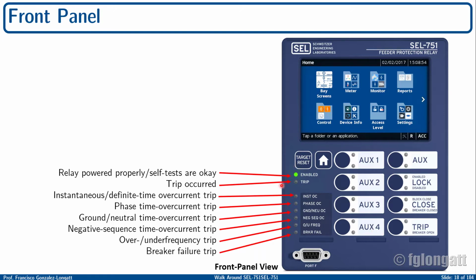Okay, here on the left hand side you will have several LEDs. Those LEDs are colored, which means that we are talking about at least 3 different colors per light. And as you can see over here, there is one to show you that the device is properly working and the self-tests are okay. Then we have here a light that we don't want to see so much, that is the trip, because we will have a fault. And here there are some indicators about possible conditions like the instantaneous overcurrent trip, phase overcurrent trip, ground time overcurrent trip, neutral time and negative sequence time overcurrent trip.